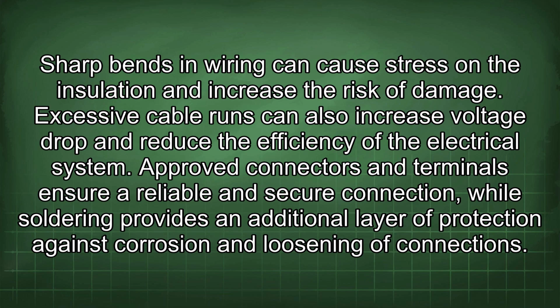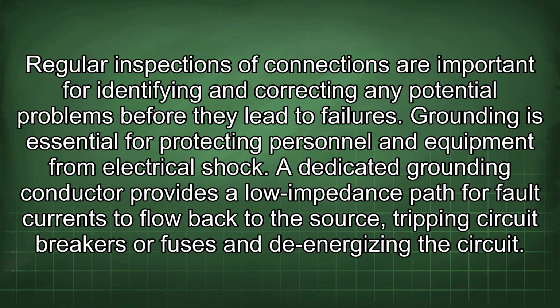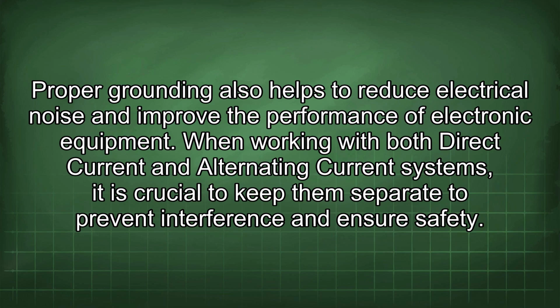Approved connectors and terminals ensure a reliable and secure connection, while soldering provides an additional layer of protection against corrosion and loosening of connections. Regular inspections of connections are important for identifying and correcting any potential problems before they lead to failures. Grounding is essential for protecting personnel and equipment from electrical shock. A dedicated grounding conductor provides a low impedance path for fault currents to flow back to the source, tripping circuit breakers or fuses and de-energizing the circuit. Proper grounding also helps to reduce electrical noise and improve the performance of electronic equipment.